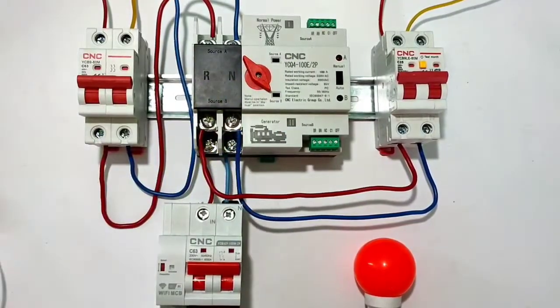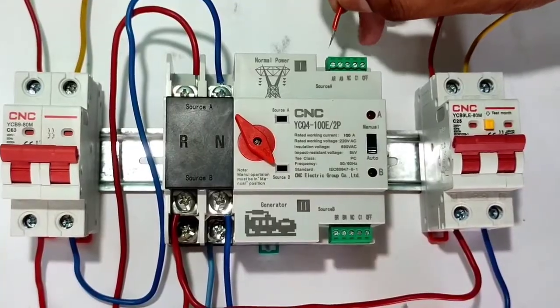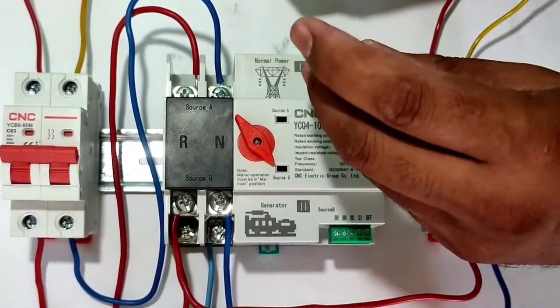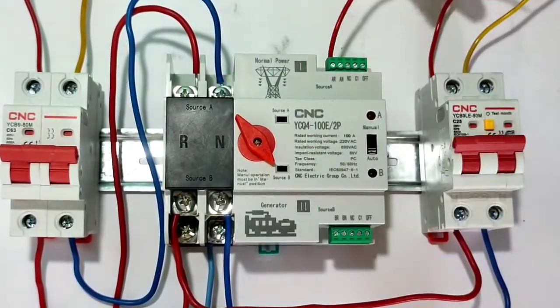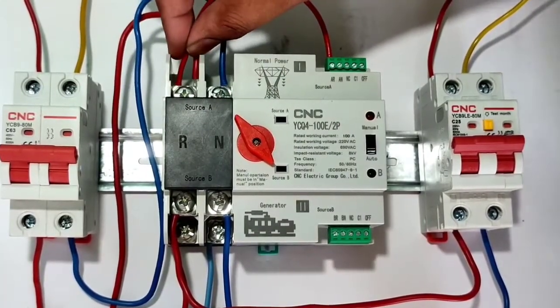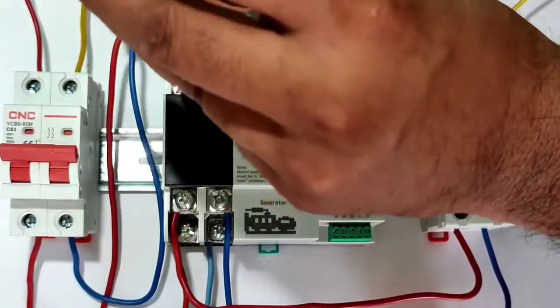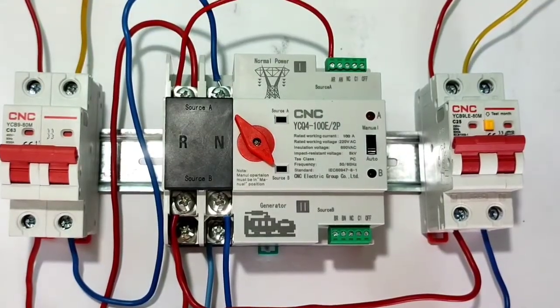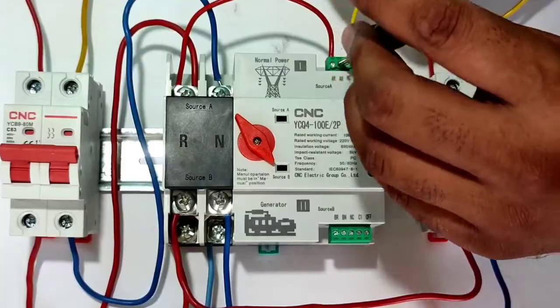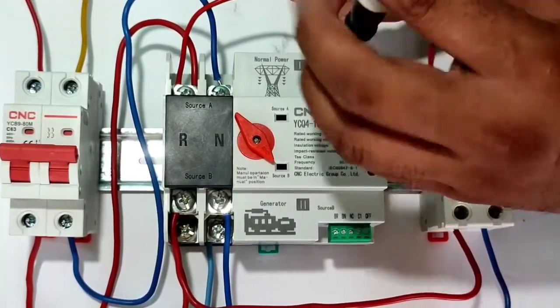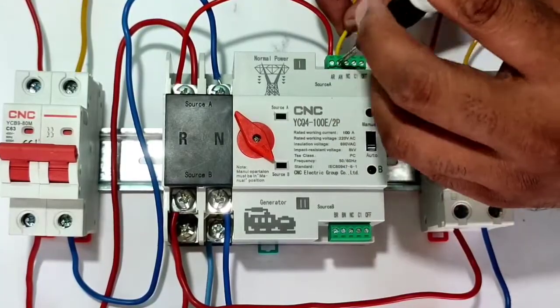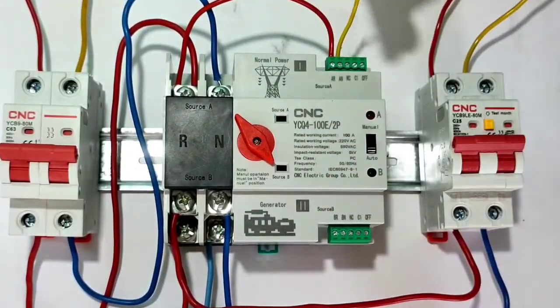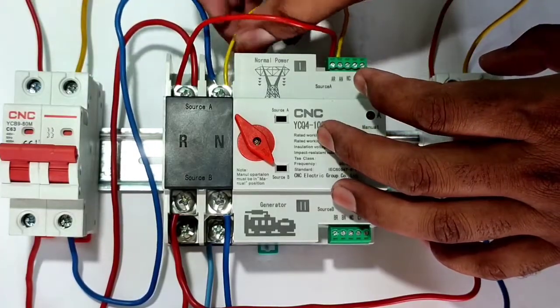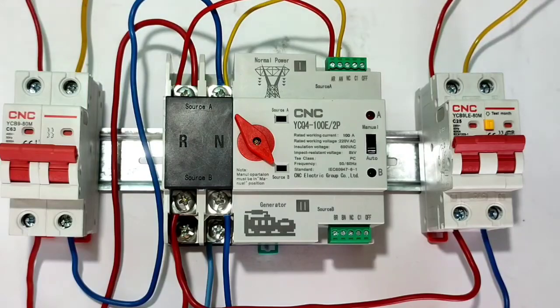Now starts the control wiring. Okay, so control wiring also is very simple. First you need to connect the AR terminal. Okay, AR terminal, you can see here. So we connect one connector from the AR terminal to the source AR terminal. Okay, so we connect here to the source AR terminal, and make sure the connection is fully tight. Okay, now for the neutral connection we connect one connector from the AN terminal to the source AN terminal. It is a very simple control wiring for this automatic transfer switch. Okay, now our control wiring for source A is done.